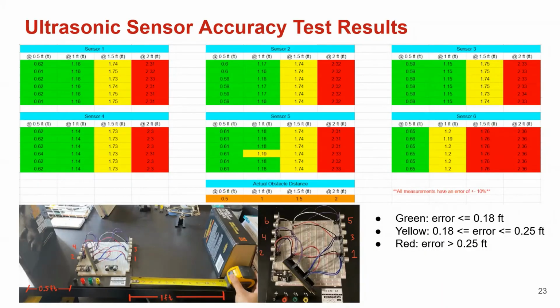This is the ultrasonic sensor accuracy test results. These tests were done using the setup shown in the bottom left picture, and they show the numbers we were supposed to be getting—0.5, 1, 1.5, and 2—compared to the actual values coming out of the sensors. As you can see, the numbers are a little off. However, they are consistent, so all we would need to correct this is a calibration curve.